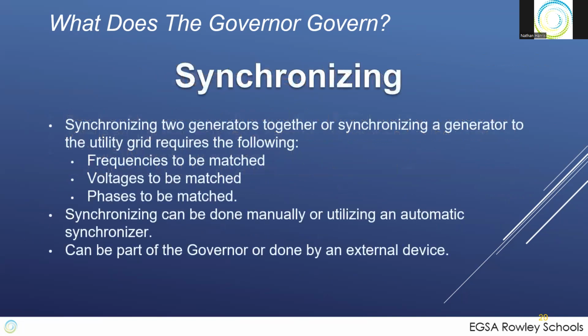Synchronizing, when it comes to times to synchronize, now you're adjusting the fuel a little bit in order to pull these generators into synchronization with either a utility or another generator. So during synchronizing, the frequencies need to be matched, and then the phase angle needs to be matched, and then we leave it up to the AVR, of course, to match the voltages and get them pulled as close as possible. It can be done by some external device or part of the governor.